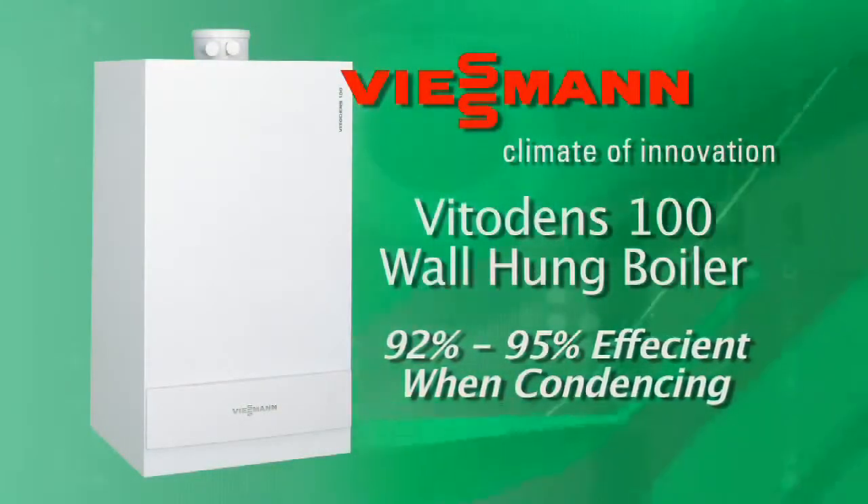When the Viessmann Vitodens is condensing, what efficiency can we expect? You're looking at anywhere between 92 and 95 percent depending on outdoor temperature and other variables. So at 95 percent, if you spend one dollar on fuel, you get 95 cents of heat out of that boiler. Conventional boilers are anywhere from 65 to 75 percent — so you might only get 75 cents on the dollar. That's a difference of 20 cents on every dollar. And if you see that condensate running — that's a good thing. If the boiler isn't condensing, it's not working properly, and you should be concerned. The more condensate, the more efficiency.